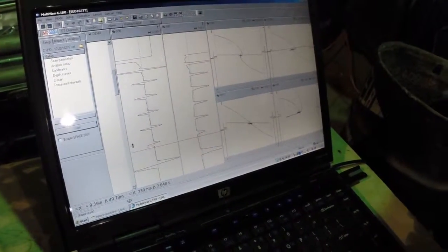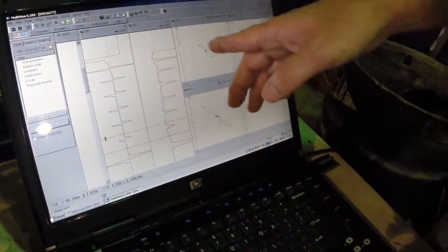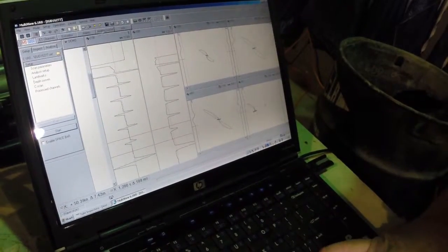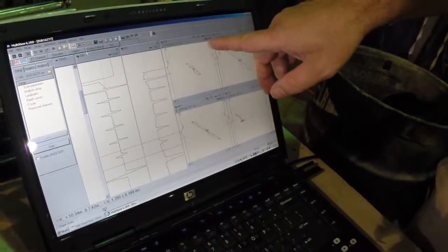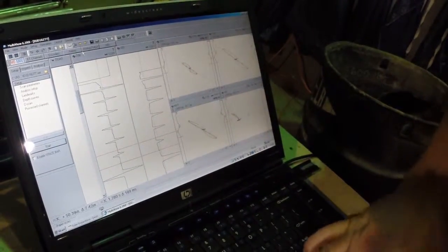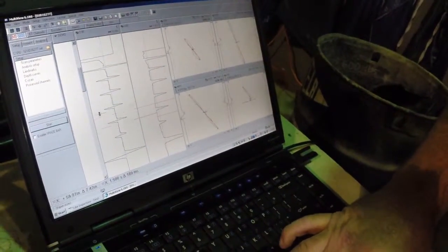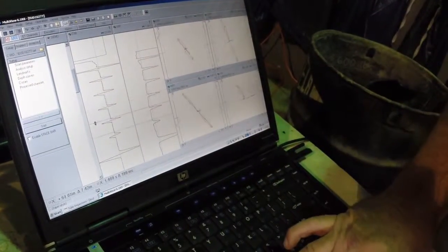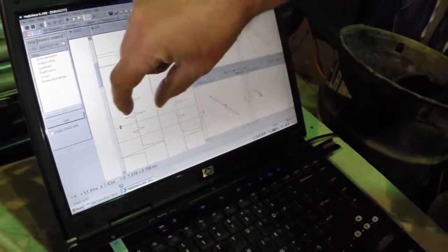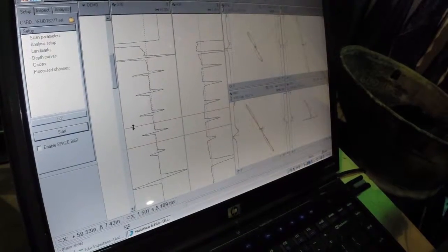And we can verify that, or we go through the calibration steps to set the equipment so we know that that indication, which is at 40 degrees, is going to represent a 100% through wall hole. So the evaluation here is within 10%, which is saying it's a 92% through wall hole. As we walk it up, we can go up to the 80%. That one's showing 86, within 5 to 10%. 60, 40. So these signatures are all representative due to the velocity or the amplitude of the indication, and what they call the phase angle is the relevant signatures of a defect.